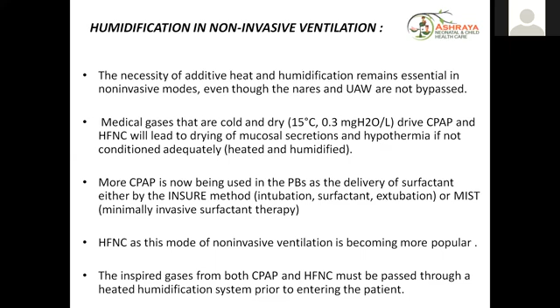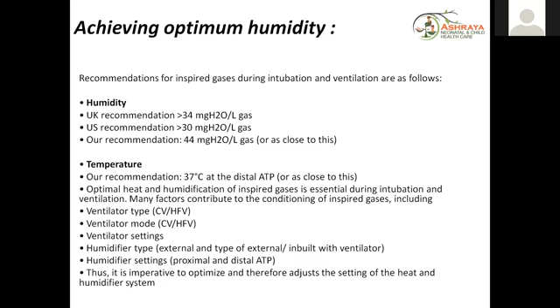So, achieving optimum humidity. Of course, the UK and US recommendations are different, but we have to reach 44 milligram H2O per liter of gas. For temperature, the recommendation is 37 degrees Celsius at the distal airway temperature probe. Optimal heat and humidification of the inspired gases is essential during intubation and ventilation. Many factors contribute to the conditioning of the inspired gases, which I mentioned previously: the ventilator type, ventilator mode, ventilator settings, the humidifier types, and humidifier settings as well. Thus, we have to look into all these and make sure that the inspired air is well humidified and heated.